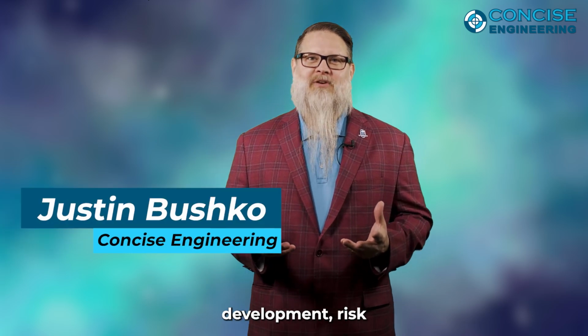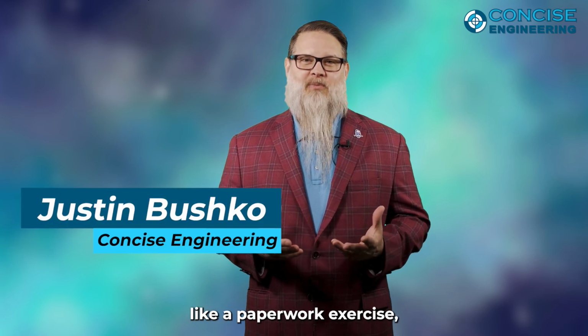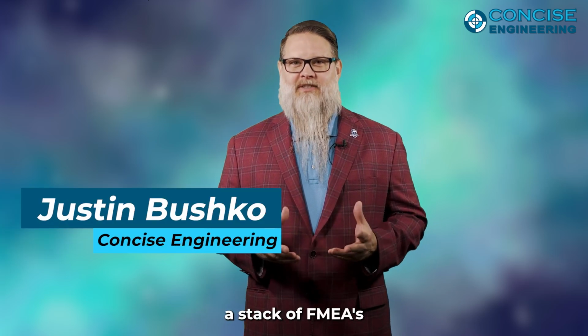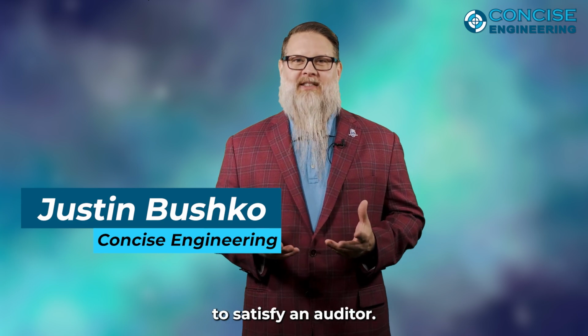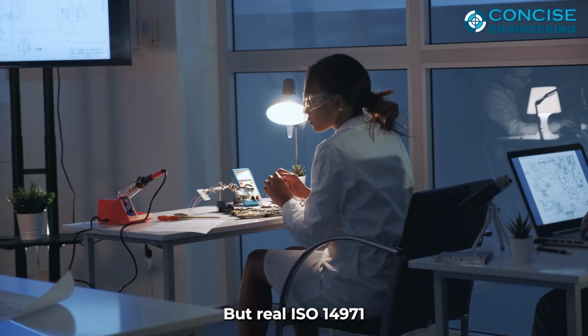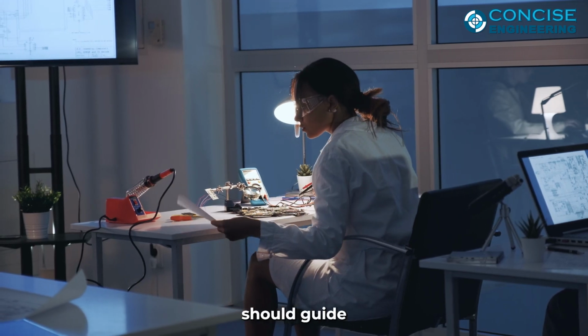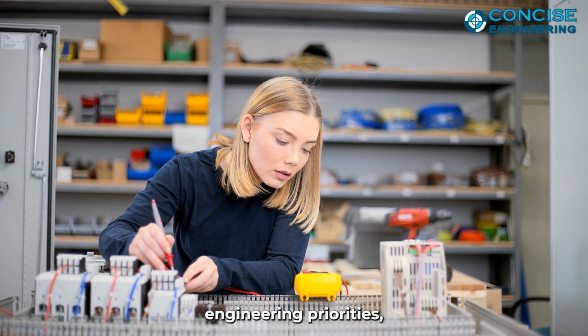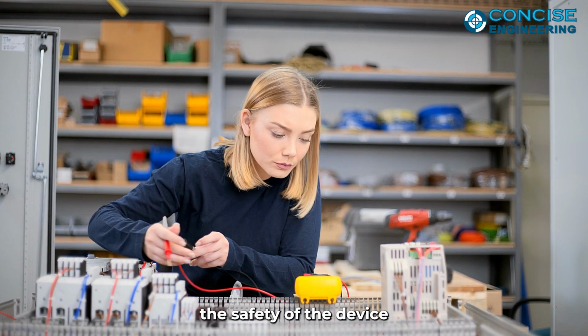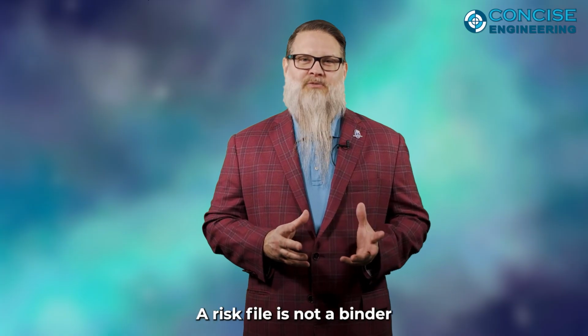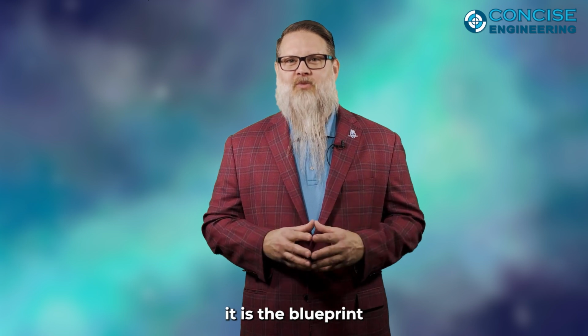In medical device development, risk management is often treated like a paperwork exercise, a stack of FMEAs, fault trees, and templates that get filled out to satisfy an auditor. But real ISO 14971 risk management should guide design decisions, engineering priorities, verification planning, and ultimately the safety of the device in the field.